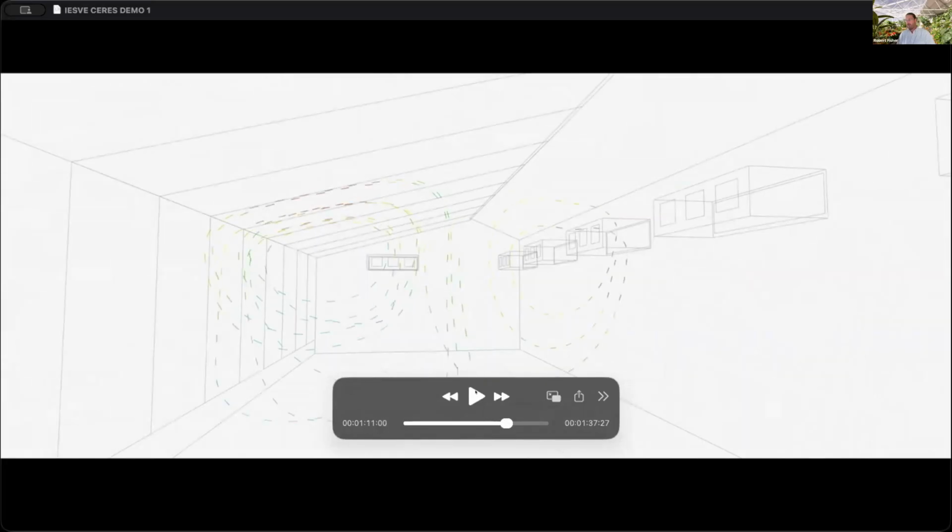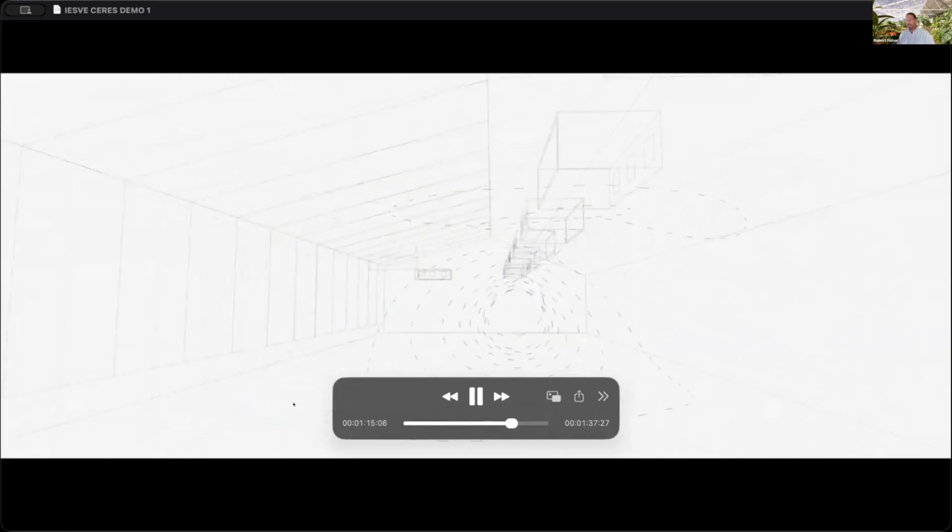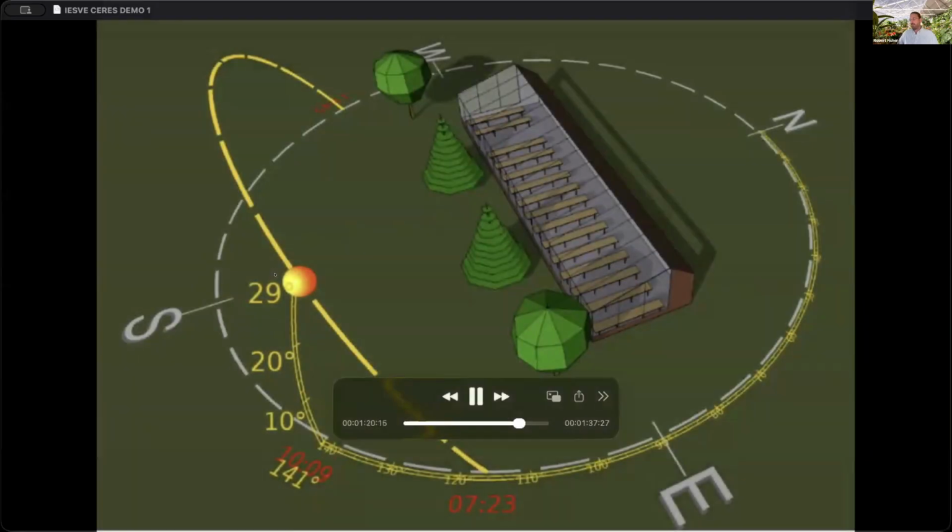This was the actual pattern that we liked of what our HVAC system was doing, because it was actually getting a really good mix against the glazing. The client requested that we remove the wall that was placed right behind here. And even though in our minds we were like, that is a terrible idea, we could then see how that air actually would flow.